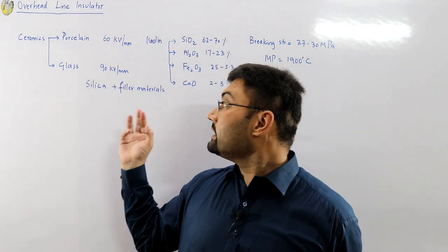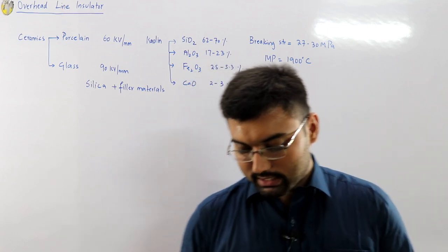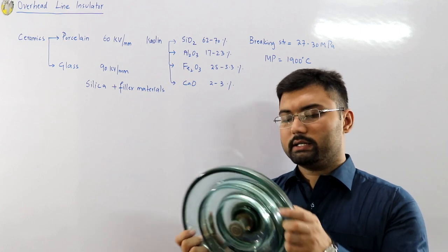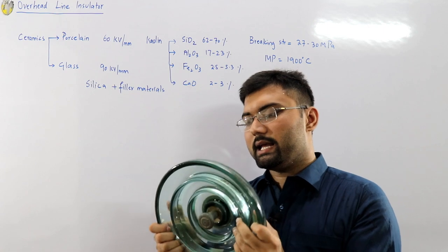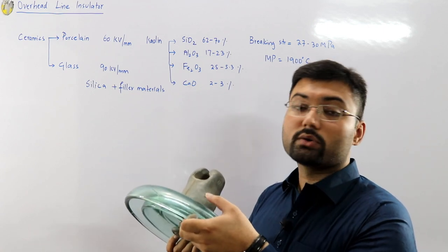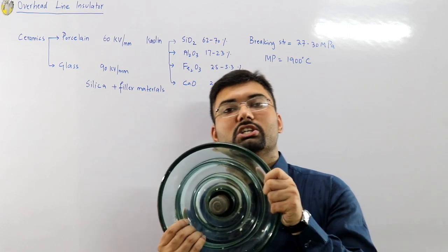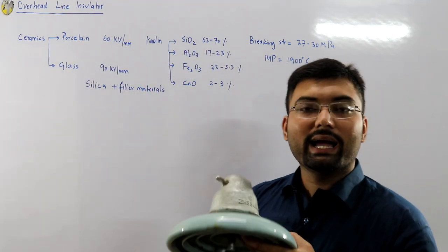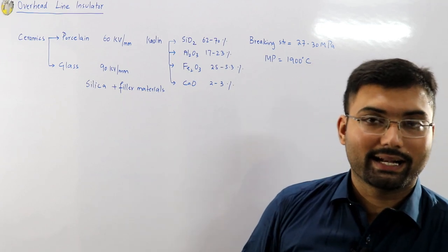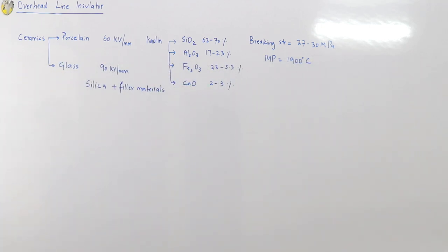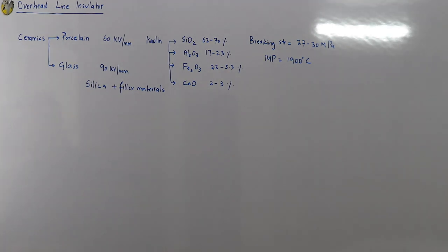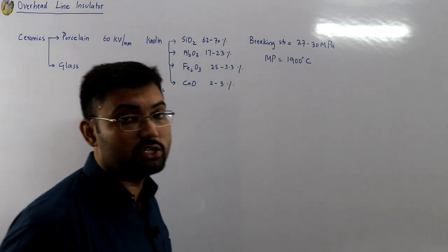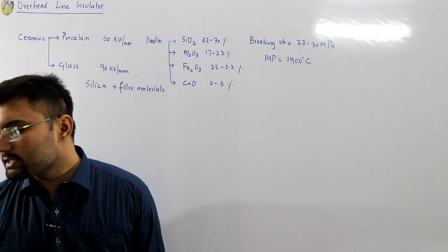I have a glass insulator here to show you the transparency — if there is any bubble, air cavity, or micro-crack, I can physically see it. Whereas for a porcelain insulator, I cannot see it physically. Also, these two insulators have significant weight: porcelain is about 5 kg and glass is about 6 kg.